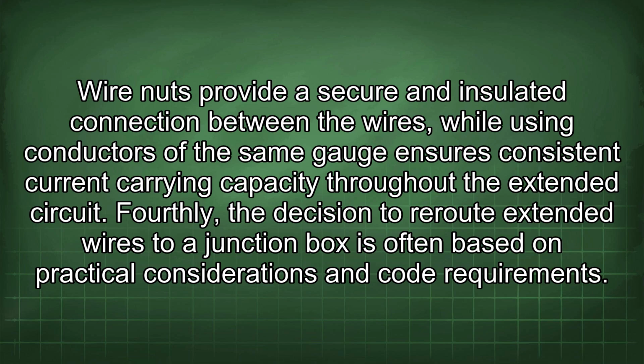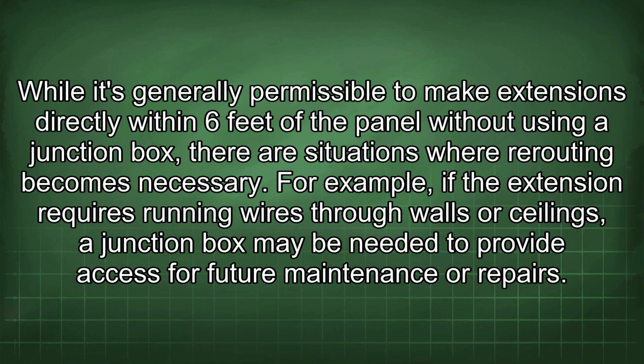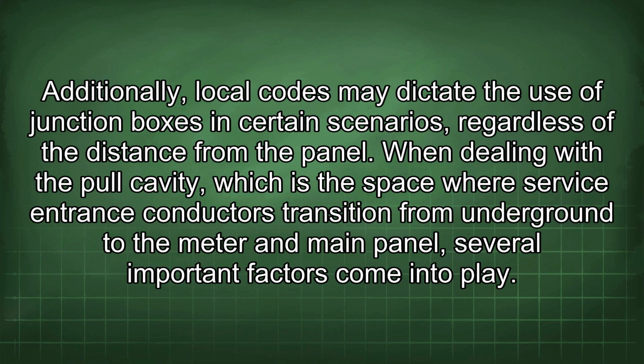Fourthly, the decision to reroute extended wires to a junction box is often based on practical considerations and code requirements. While it's generally permissible to make extensions directly within 6 feet of the panel without using a junction box, there are situations where rerouting becomes necessary. For example, if the extension requires running wires through walls or ceilings, a junction box may be needed to provide access for future maintenance or repairs. Additionally, local codes may dictate the use of junction boxes in certain scenarios, regardless of the distance from the panel.